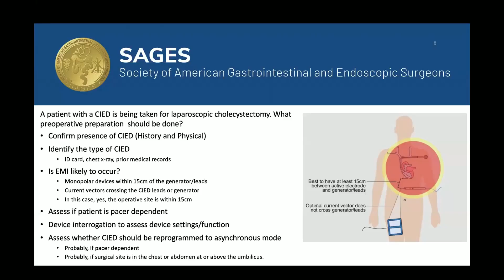So again, we're talking about asynchronous mode. The device rep, electrophysiologist is not present, and the device rep says, do you want this in asynchronous mode? So again, for pacemakers, the asynchronous mode keeps it delivering a constant rate, and then it prevents any detection, and that prevents incidental arrhythmias. This EKG over here kind of shows how you can cause stacking of the patient's own electrical rhythm with essentially pacer fires from misreading electrical surgical instrument signals, and you can induce a ventricular tachycardia. This EKG over here is just showing that the pacer spikes with each QRS complex.